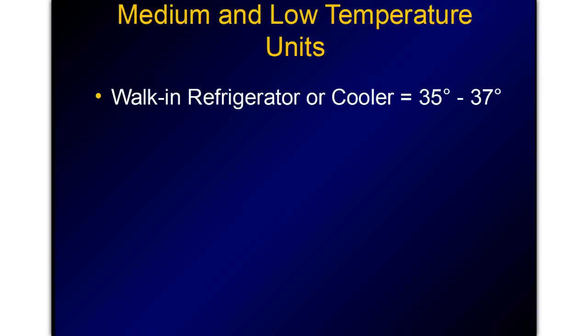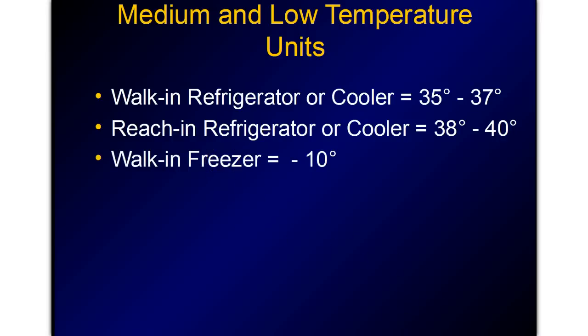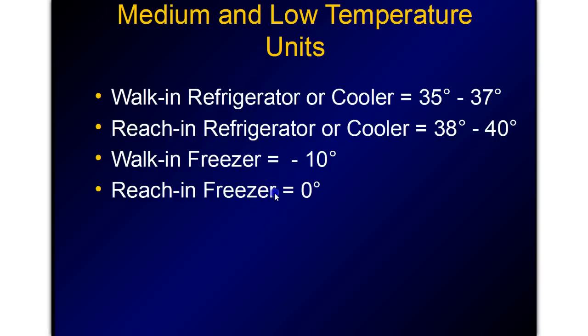We also talked about the different temperature ranges of commercial refrigeration. This course is going to discuss medium and low temperature units. Walk-in refrigerators and coolers are 35 to 37 degrees, and reach-in refrigerators or coolers are 38 to 40 degrees. Walk-in refrigerators are for large bulk, longer-term storage, while reach-in refrigerators or coolers are for convenience and daily use. Walk-in freezers are at minus 10 degrees and reach-in freezers are at zero degrees — the same concept applies, with walk-ins for long-term storage and reach-ins for daily use and convenience.